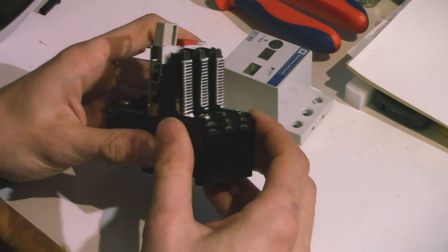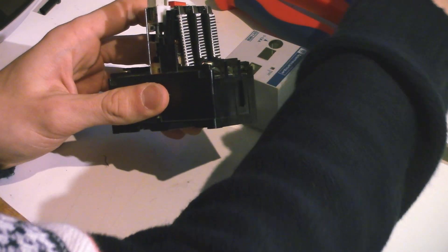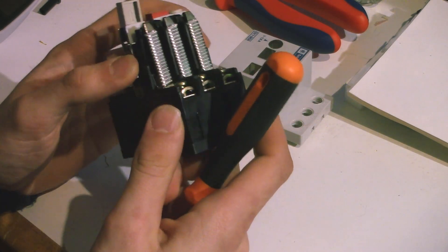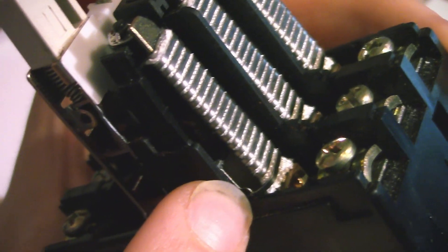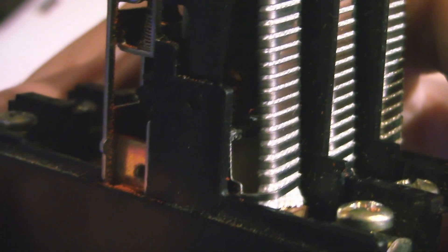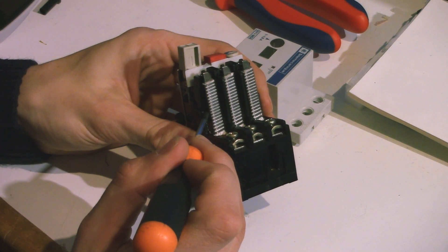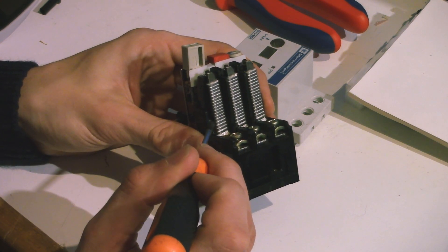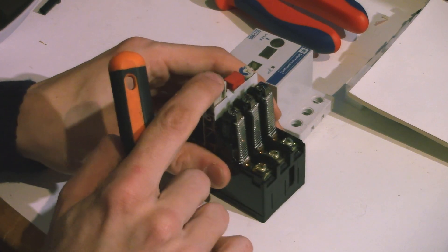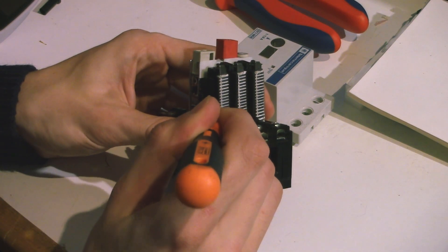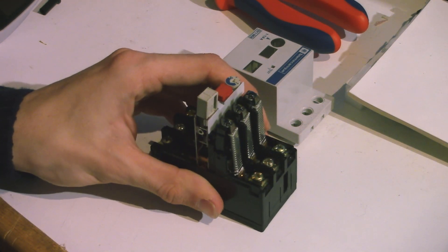And this is actually a magnetic mechanism, and this is actually very hard to see. But if you look carefully, you can see that there is a coil right there. It's wrapped in some white electrical tape-ish stuff. And that coil attracts a piece of metal which is attached right there. And if that piece of metal is pulled down into the coil by the magnetic field that it creates, that also, as I will demonstrate right now, unlatch the spring and open the switch.